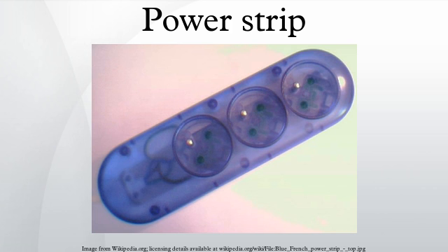The surge-induced triggering of MOVs can cause damage to an upstream device, such as an uninterruptible power supply, which typically sees an overload condition while the surge is being suppressed. Therefore, it is recommended not to connect a surge-protected power strip to a UPS, but instead to rely solely on surge protection provided by the UPS itself.